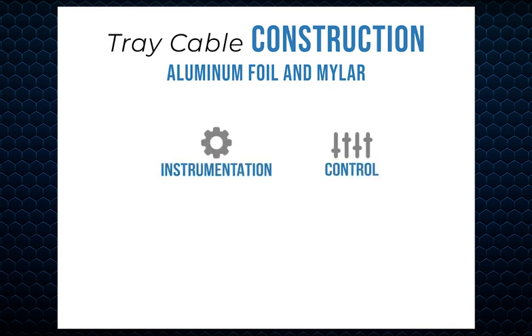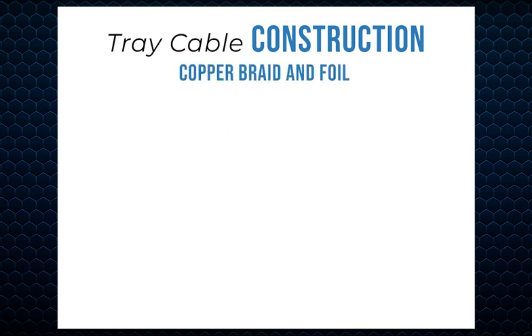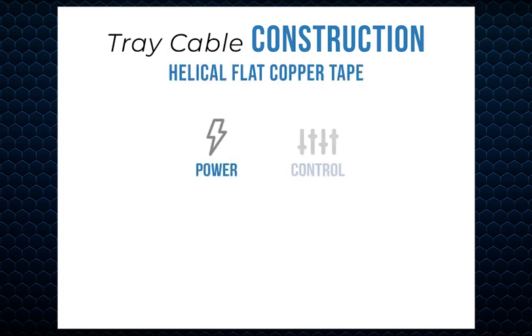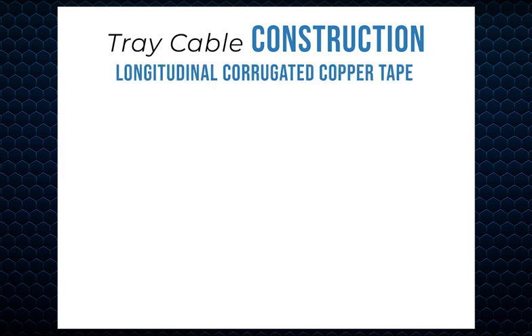There are 4 common shielding methods: aluminum foil and mylar, used in instrumentation and control; copper braid and foil, used in power, control, or instrumentation; helical flat copper tape for power and control applications; and longitudinal corrugated copper tape primarily used in utility. The shield can be applied helically or longitudinally over the cable core.